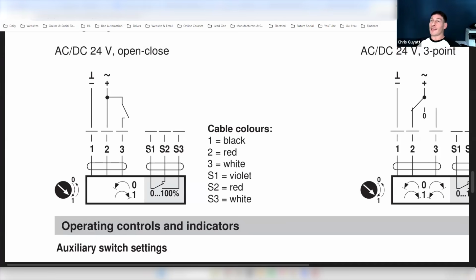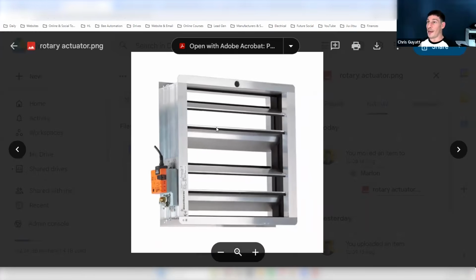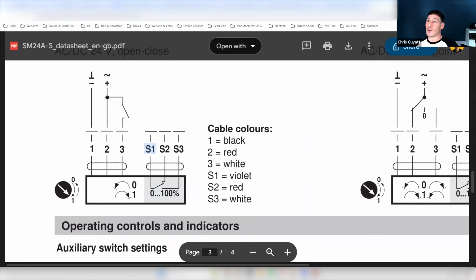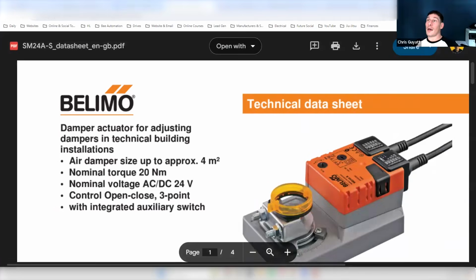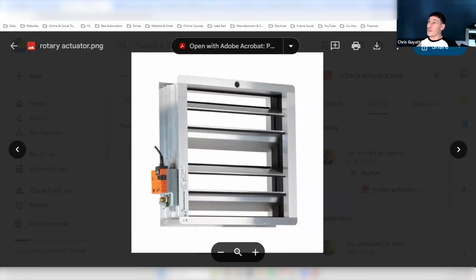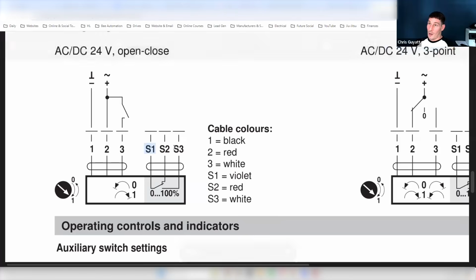Yeah, so that's that basically. These are our auxiliary switches. So S1 switch, and a switch kind of indicates that it's an output. It's like we're sending a signal out. That's probably not a good way to think about it, actually. Ignore what I just said there. But yeah, that's what they're doing. It's telling us the status of this damper. Is it fully open like it is in this position here? If that was the case, we'd have a signal going out on S1. And then when it's fully closed, we'd no longer have a signal going out on S1. We'd have a signal going out on S3. Or sorry, that might be the other way around, but you get my point.